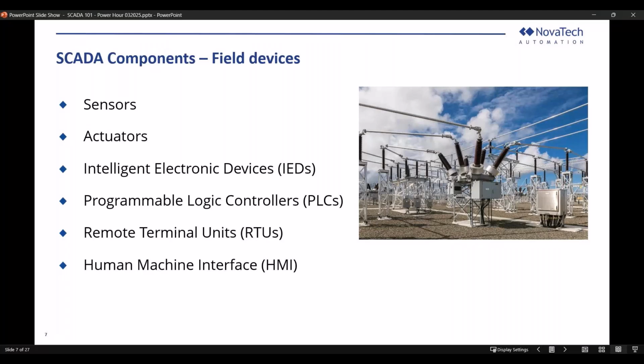And then remote terminal unit, RTU. This I need to dig a little deeper into. Saurabh will go through it as well. But the terminology I want to clarify, because I got confused as a new grad: remote terminal unit, the definition of it, is the actual computer, the electronic device that collects data, that pulls data from your IEDs and your I/O modules, and it can do logic in it, it can convert the protocols, and it can send data up to your control system. So that's what an RTU is.